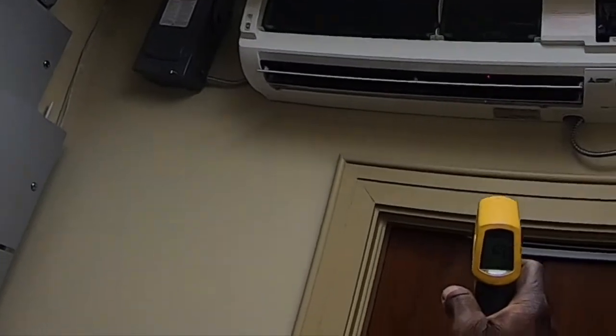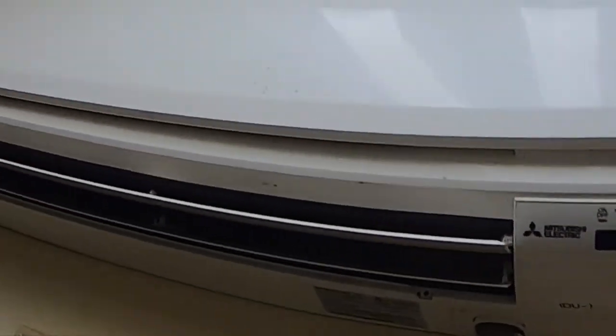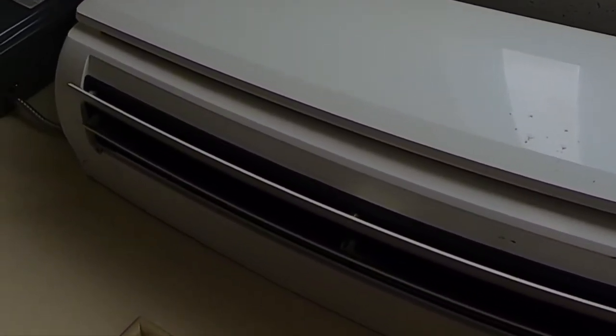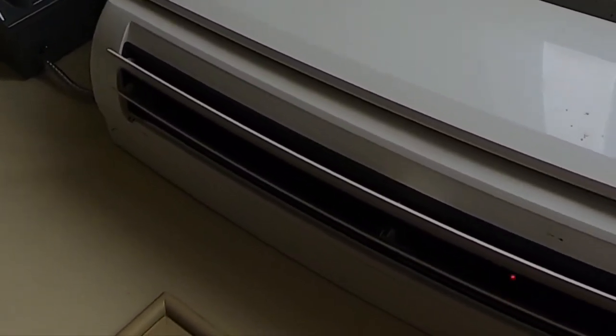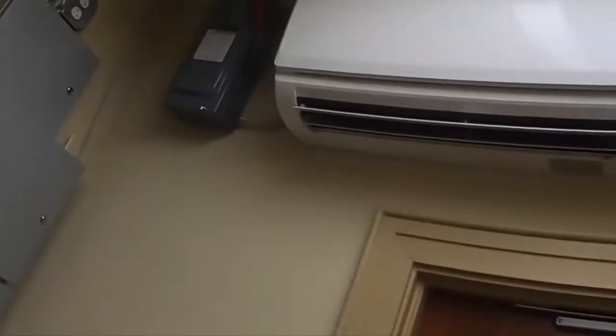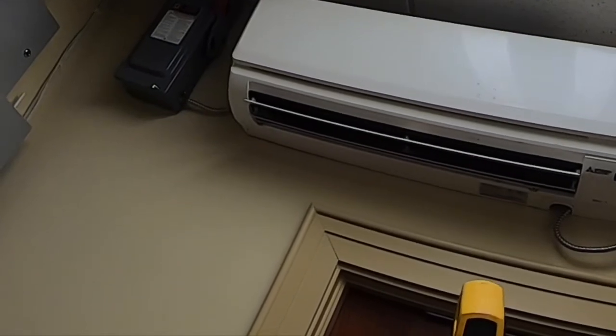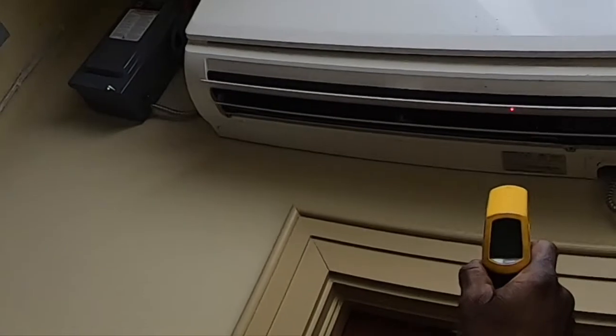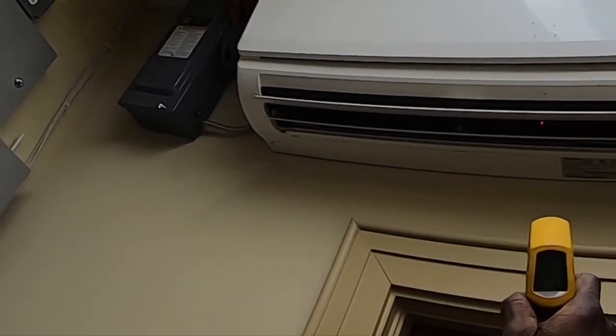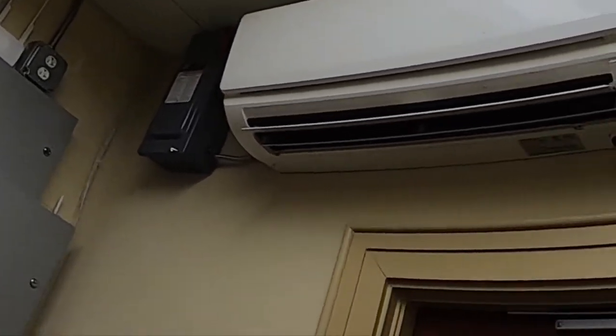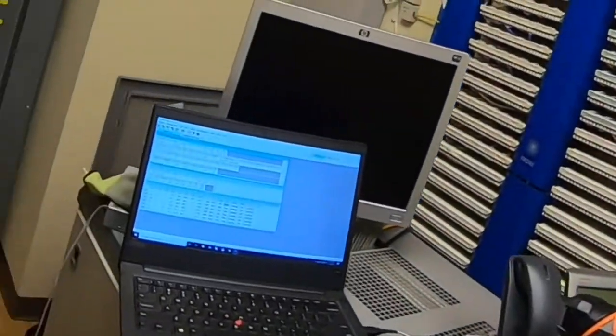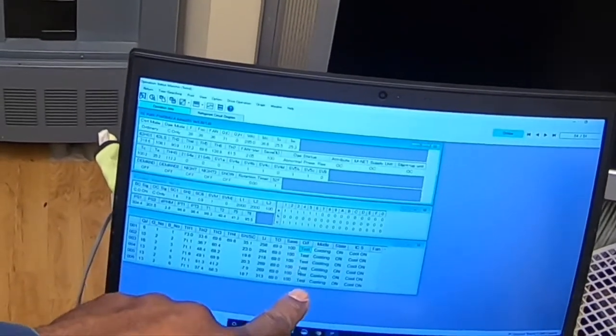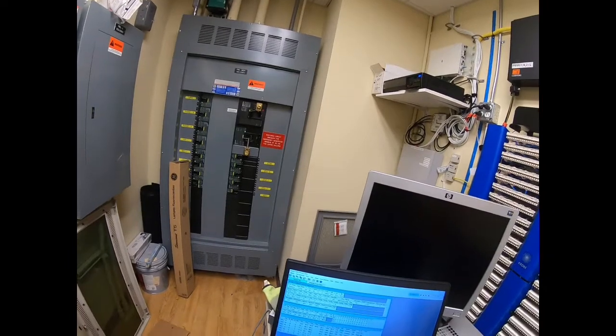I'm curious about the temp coming out of here. Let's take a look. 65, that could be much better, so that's not that great right there. It should be 55-degree air coming out of there. Yeah, 64, so there are some other underlying issues going on as well. There we go, 61, 62... 61, still not ideal, but I'm going to keep monitoring. There we go, everything's in cool mode now, everything's in test, everything's in cool. Let it run and see what the superheat does to make sure everything's looking okay.